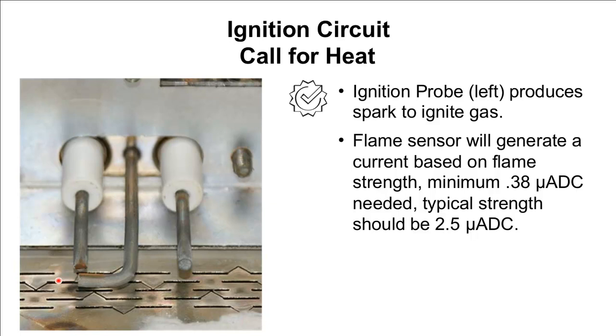We get ignition. At this point, our flame sensor is going to react with that flame and produce a DC microamp signal. The minimum signal needed to keep the unit lit is 0.3 DC microamps. Typical strength of the signal is around 2.5. If you're running the unit from a cold start, it may get up towards 4 or 6 even. But once the unit's at temperature and it's cycling, 2.5 is the average.